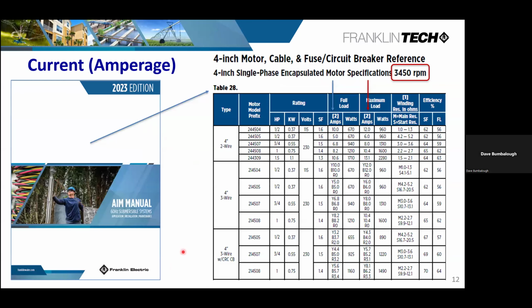Now, according to manufacturing, you want to make sure you stay within the recommended amp ratings of that piece of equipment. In this case, a submersible typically has two ratings. Most motor manufacturers will usually just stamp one rating on there. This is the max amps that equipment should pull. At some point, I'm sure we'll do the same thing. We'll get rid of this full load amperage and just say, look, this is the max amps. As long as you're under that, you're good to go. But we've not changed that yet today, and most manufacturers still list the same thing. They'll list the full load, which is the rating of that motor at its horsepower range.